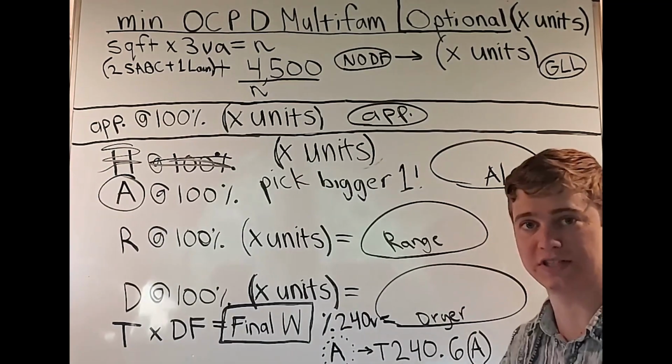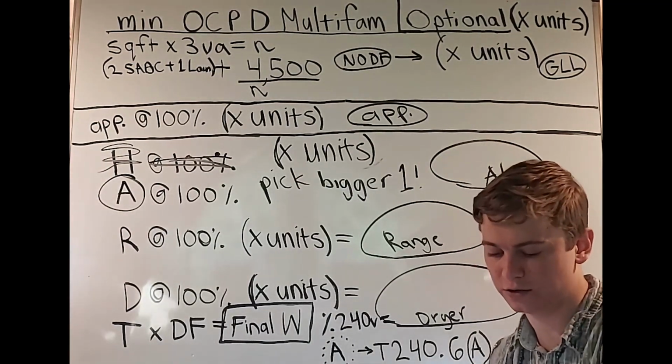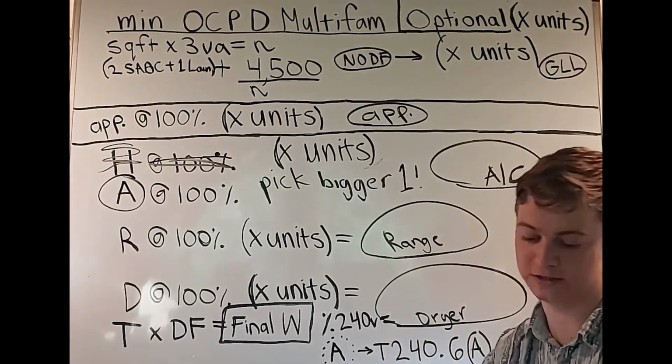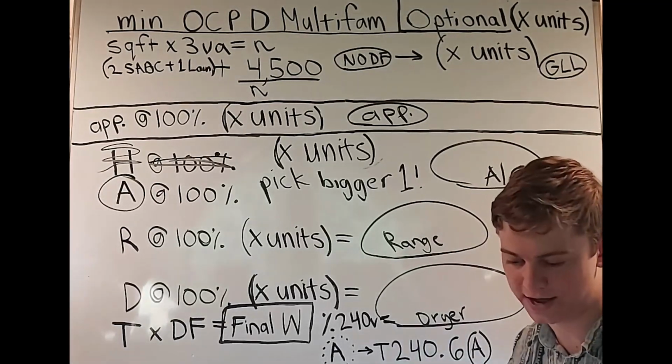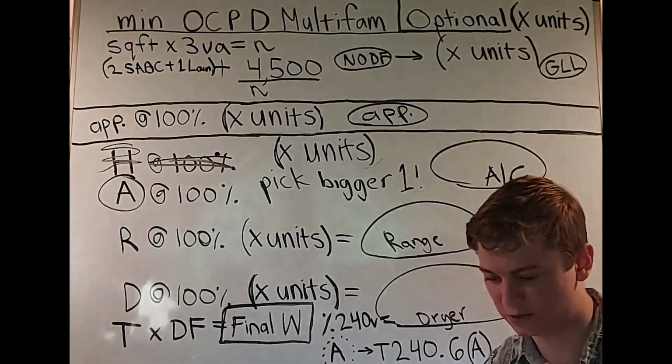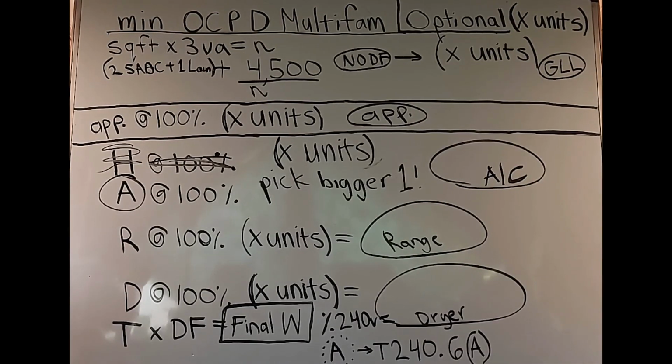Okay, now if you want to see what size wire you're using, you're going to be using table 310.12, if your service is between 100 and 400 amps. And if you have further questions about this, read article 310.12. Okay, so that is it for the summary as well as the page layout. This shows you how you can lay out your page if you're going to solve this.